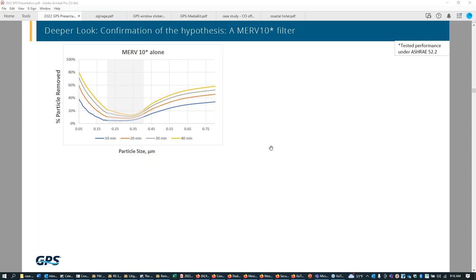What we found is that a MERV 10 filter by itself does a pretty good job after about 40 minutes removing this calibrated cigarette smoke, but you can see very clearly demonstrated here that weakness in the filter between 0.25 and 0.4 microns in particle size. After 40 minutes, we're well under 20% removal efficiency in this size range. Meanwhile, we get up over 50% removal as we get closer to 1 micron with this MERV 10 filter.